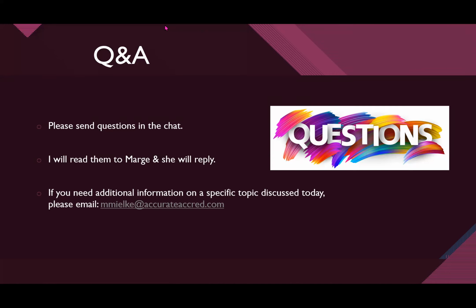And then that separate question was, and I don't know if this person's at the same center, from Catherine. She said, we have a door that separates the door and is 1 hour fire rated. The punch code lock on the door is also fire rated. We also have a sign on the door that states it is not a fire exit. Oh, so I think maybe they are at the same center, sounds like. And then Anita said the metal signs had to be removed in order to pass our fire door inspection.